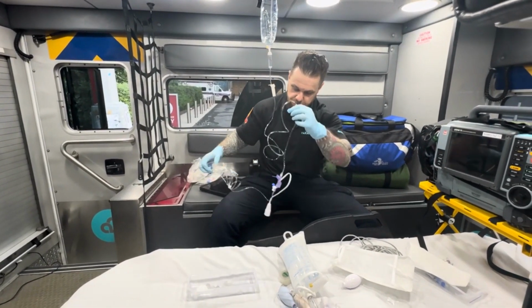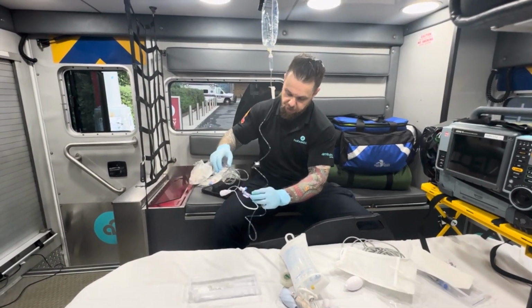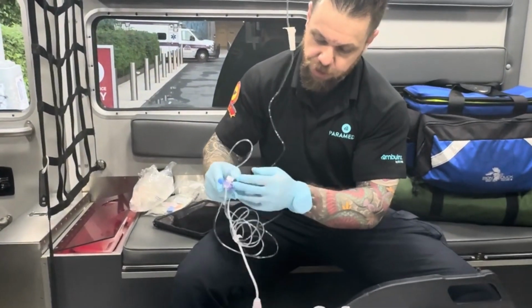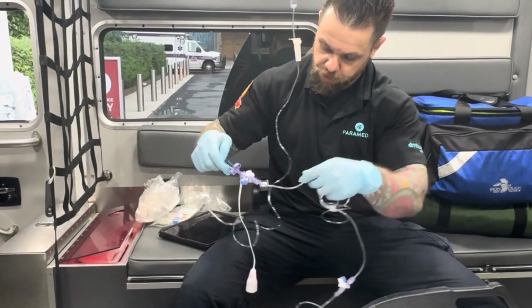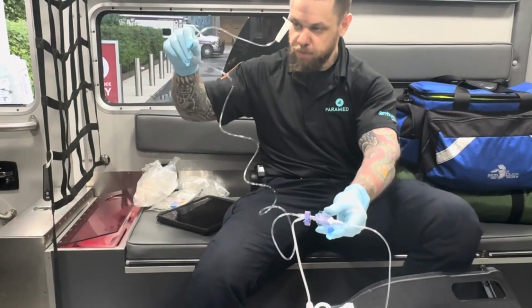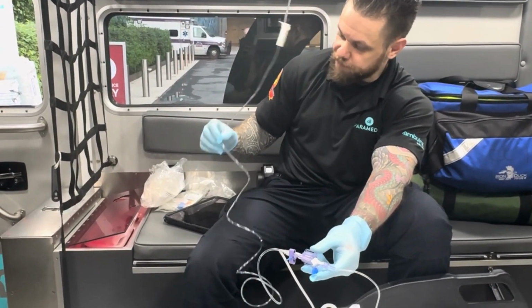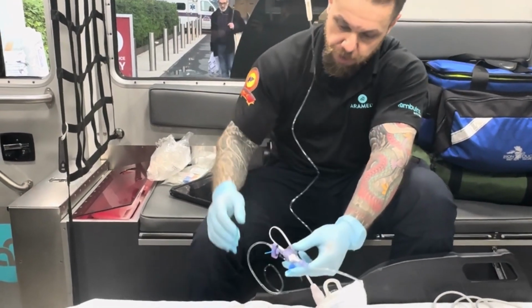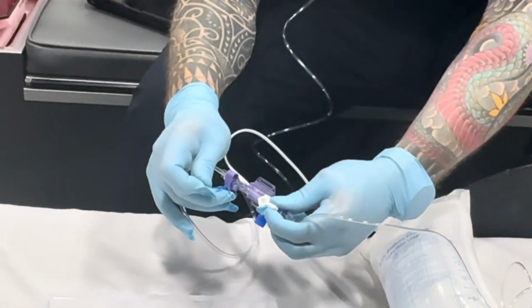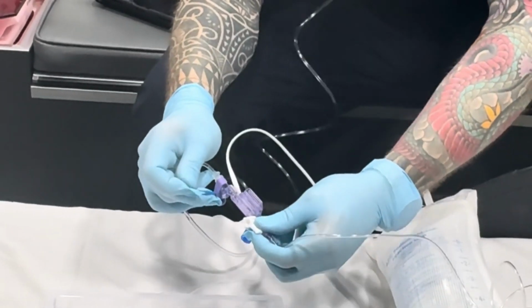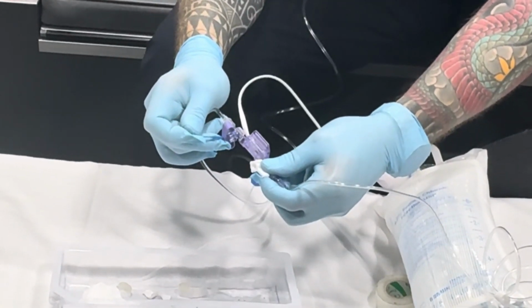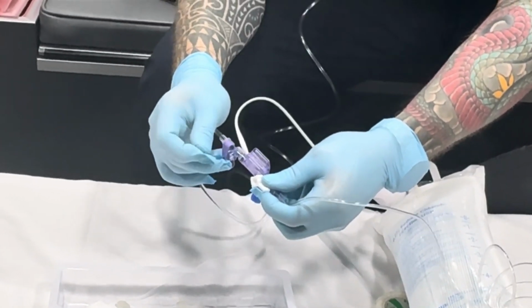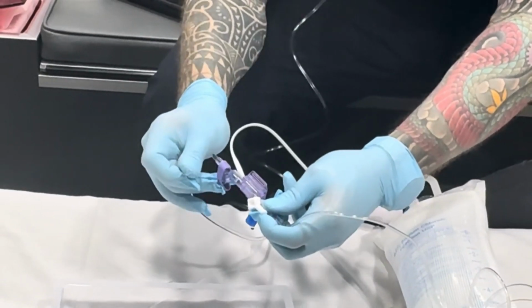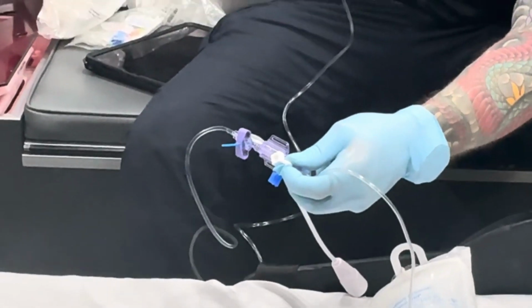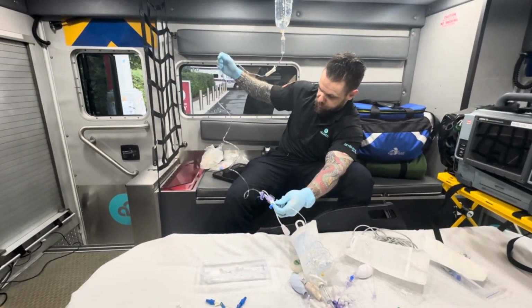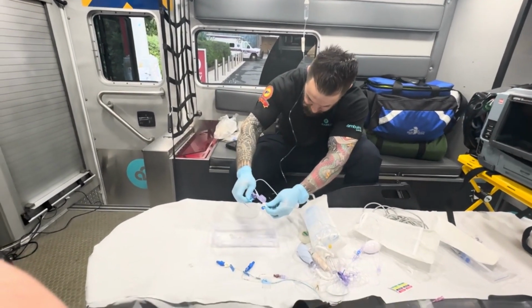So what I'm going to do, you will see, I'm going to pull on this pigtail, and the saline should come out of this port right here. So let me make sure you guys can see. And what I'm watching for is making sure all these air bubbles come out. So I have no air bubbles, period, in the system. So I'm going to open it here, and you see all the air bubbles are coming. So it's open here, and as I'm pulling the pigtail, you see the fluid coming out. So I look at my tubing, I see no air bubbles. So this looks clear to me. If you saw any more air bubbles, you just continue doing this.